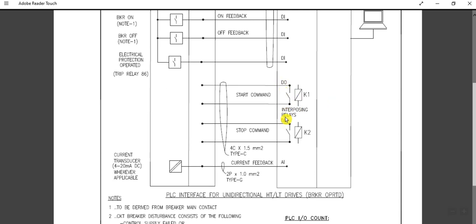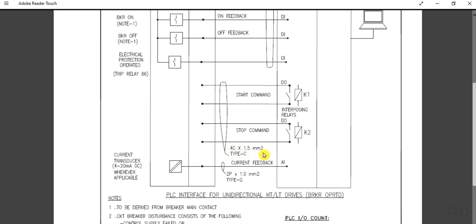Now coming to the DO signals — digital output. These are for the circuit breaker start command or stop command. When we want to operate from the DCS or PLC, we give a start command or stop command, which are digital outputs, not feedbacks. For this we need interposing relays K1 and K2: K1 is for the start command and K2 is for the stop command. These interposing relays can be located inside the switchgear or in the DCS/PLC I/O cabinet. Here we have considered a 4-core, 1.5 square mm cable.